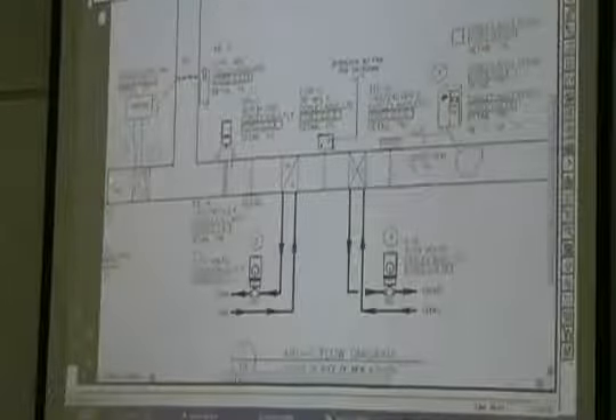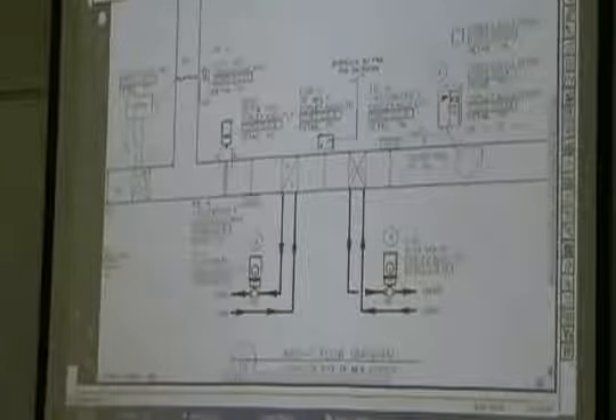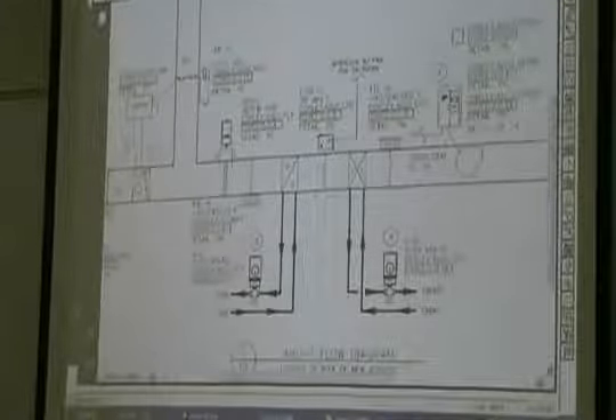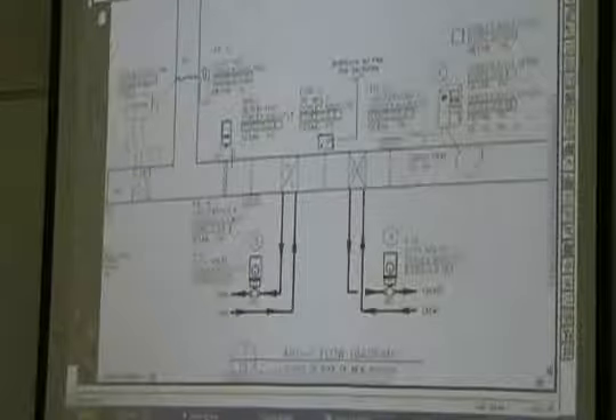So what did we set for fresh air in the past? We just arbitrarily picked a number, or we had the balance guy measure the outdoor airflow and tell us, okay, that's good, and whatever that position was on that outdoor air damper, that was our minimum. We wouldn't go below that. Well, with VAV, that worked okay on constant volume units. With VAV units, that doesn't work.